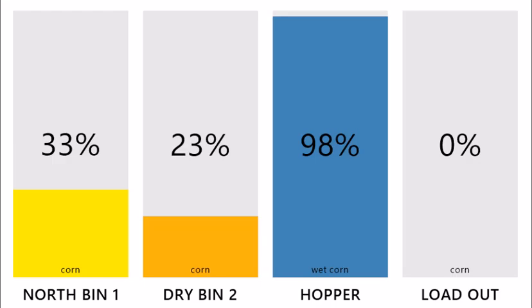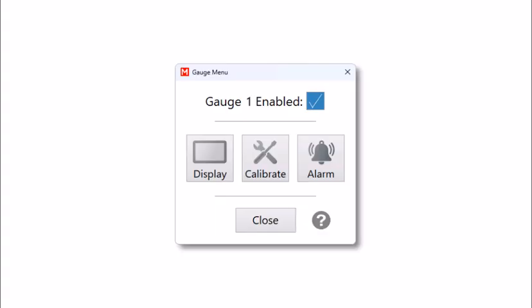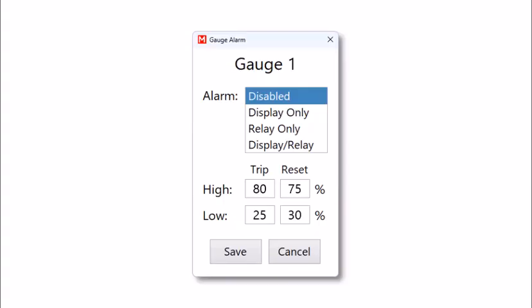The last step in our setup is creating our alarm framework. Like we did with the other steps, we're going to press and hold on the fill bar to open the gauge menu. Then we'll click on Alarm to open the Gauge Alarms screen. And we can see that there are a few options available for alarms. We can select Disabled, Display Only, Relay Only, or Display/Relay. If disabled is selected, as it is now, the system will not generate any alarms. If display only is selected, the full view monitor will show an alarm by blinking the fill bar red. The alarm will be generated based on the numbers entered into the bottom section.